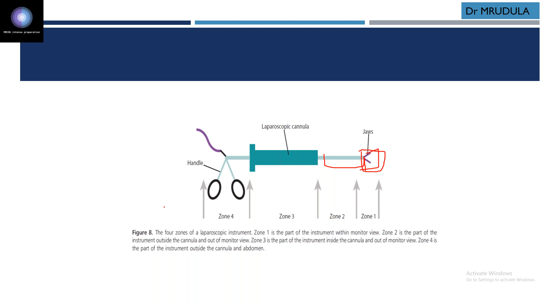So there are 4 zones of laparoscopic instruments. Zone 1 is usually the tip of the electrode. Zone 2 is the part of the instrument which lies outside the cannula, and it is usually out of the monitor view. What we usually do during lap surgery is that the tip is always visible, but this is the area which remains invisible through the laparoscope. Then zone 3 is the part which is inside the cannula, and it is also out of monitor view. Zone 4 is the part of the instrument which lies outside the cannula.